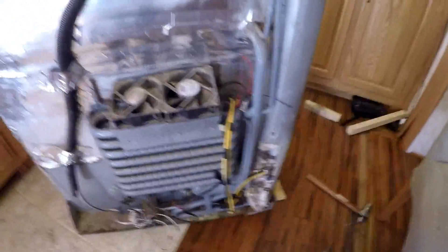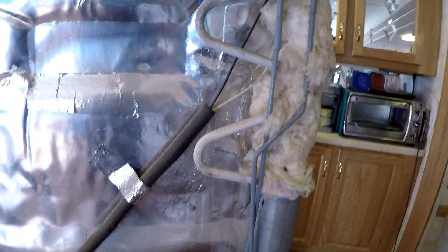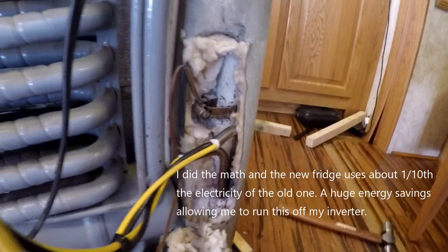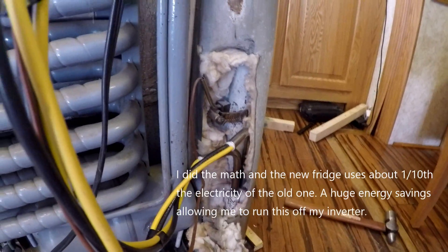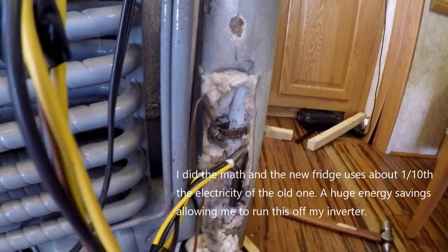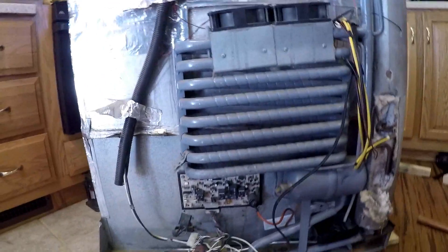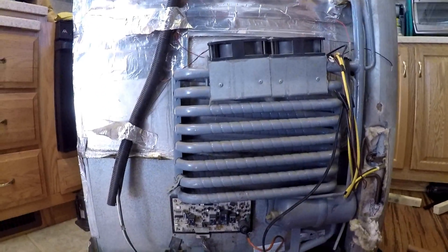Here's the unit that I actually had replaced — this whole unit you can see has been spray-painted gray. That was replaced in 2013. It took about two hours and it wasn't that bad, but obviously it only bought me a couple of years, so it was a pretty expensive fix at about 700 bucks. Over here those are the heating pencils — the heating elements are 225 watts apiece. I did replace those as a first step in troubleshooting. I also replaced the gas burner, which I knew was plugged up. It wasn't cooling well as I was driving down the road, which is a common problem with these Norcolds — they just never seem to want to stay very cold when you're driving.